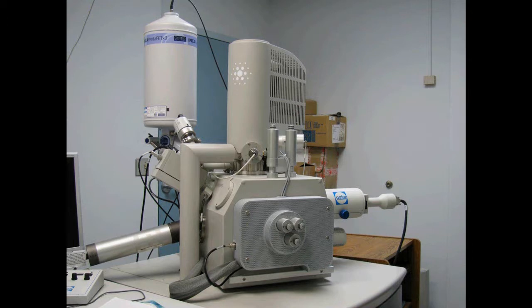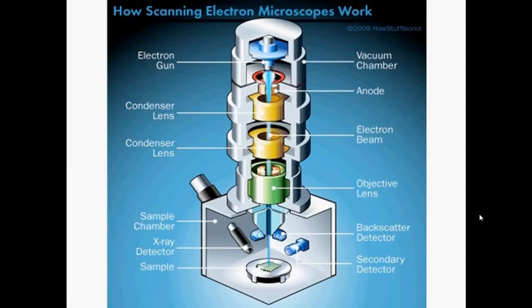The main parts of the SEM are the column, the chamber and the table. The electron gun on top of the chamber produces a steady stream of electrons which hit the sample. The detectors in the chamber collect the electrons discharged from the top surface of the specimen and produce images. The lenses present in the column are made of magnets and they help to focus the electron beam on the sample by bending the path of the electrons. Vacuum conditions are necessary to ensure that the beams don't get deflected out of their path by the air particles.